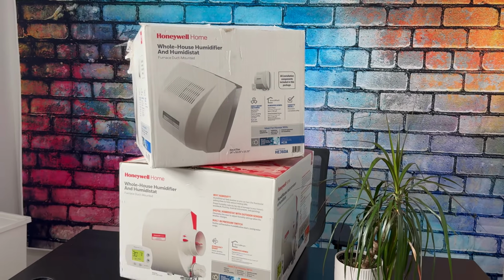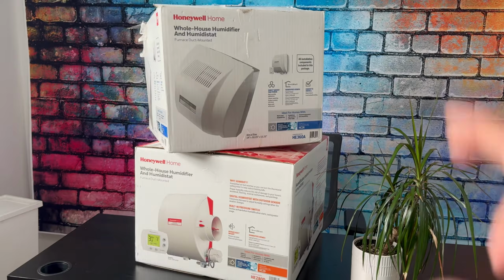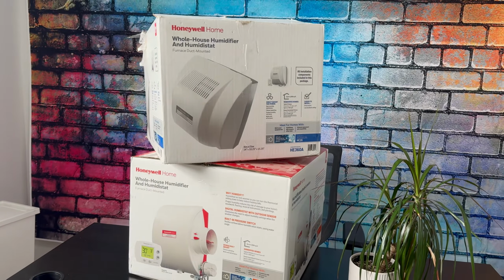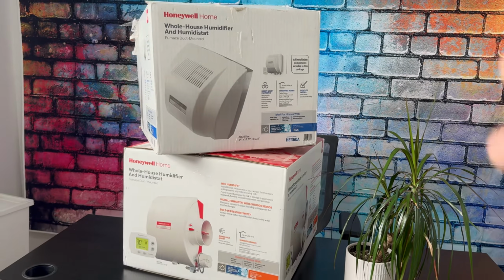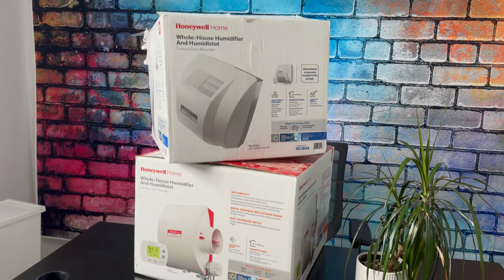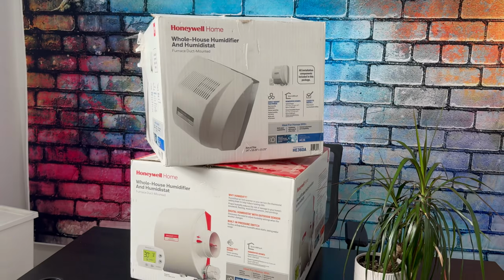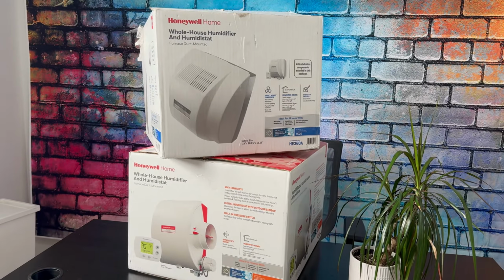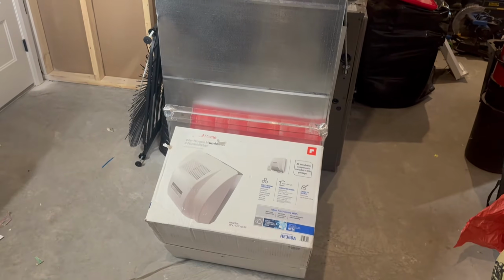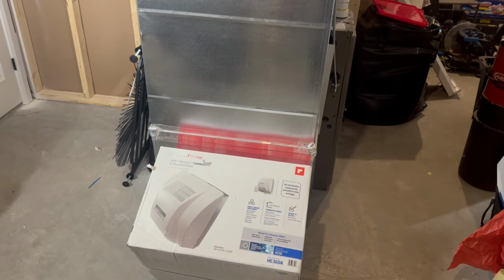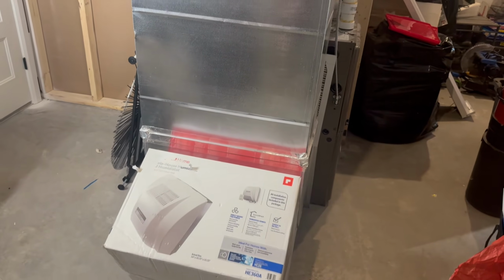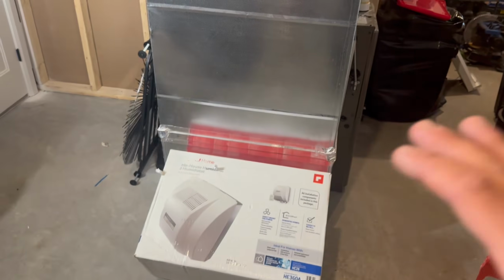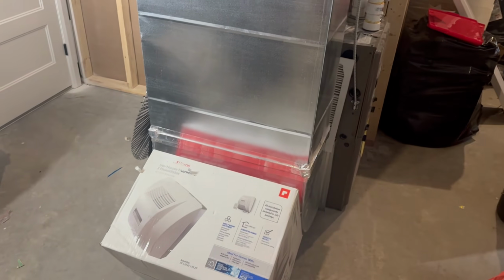I do want to note that the installation between these two are very similar. In fact, they're almost exactly the same with a very slight variation. I'll be walking you through the steps for the fan-powered direct mount, and I'll include steps for the bypass duct humidifier. To make things simple, if you have a direct mount fan-powered humidifier, you want to try and mount this on the supply side of the ductwork.